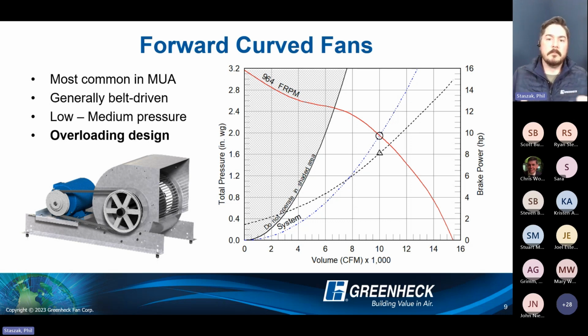And if it's not there, this is an example of a forward curve fan. The blue line is your system curve. Your operating point is the circle. So if we take a look at a perfect scenario, a real world situation where we've calculated our static pressure, and our system now with internal static pressure and external static pressure is just under 2 inches total water column, and we want to move 10,000 CFM. Now we follow that line down to the dashed black line. That's where our brake horsepower is going to be. So for this particular forward curve fan at just around 2 inches of total static pressure, it's going to require right around 8 brake horsepower to move that airflow at 964 fan RPM.